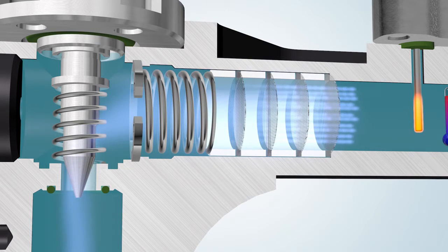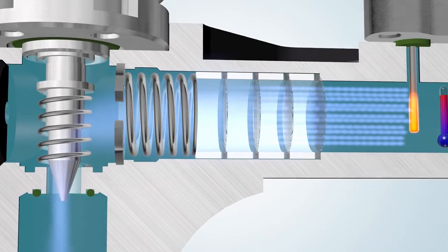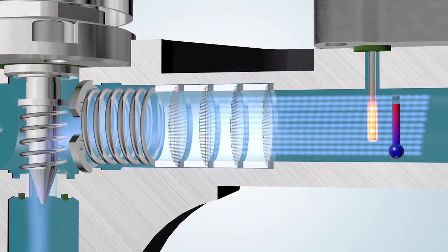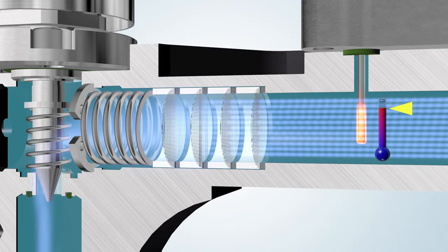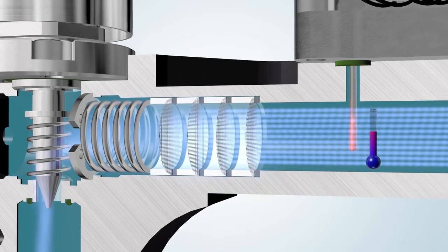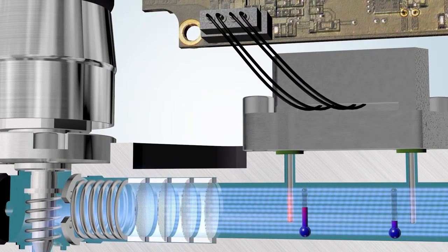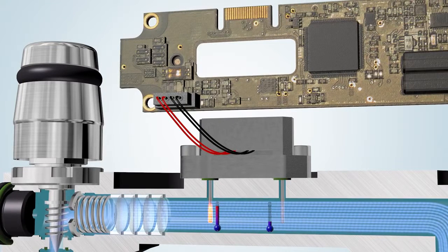Now the gas passes through the flow straightener, thereby creating the laminar flow profile that assists with stabilizing the measurement conditions. The flowing gas cools the heater probe, and the comparator registers that the temperature difference between the two probes decreased. More energy is applied to the heater probe to maintain the desired constant temperature difference. This increase in heater energy is directly proportional to the mass flow as originally set out in King's law. The higher the flow, the more heater energy is needed.